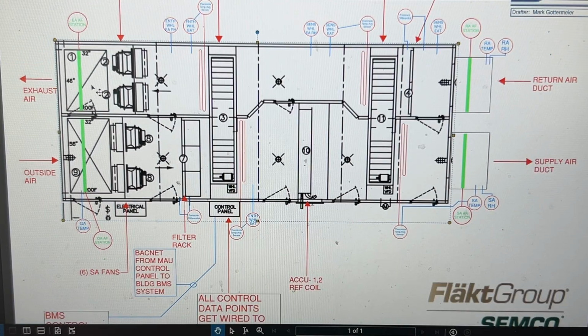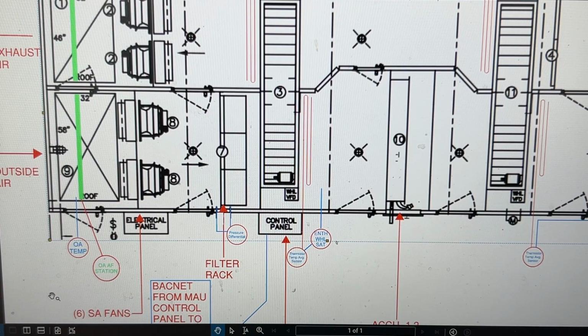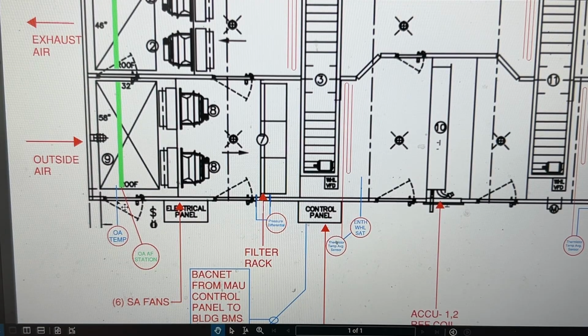And the purpose of these, we've got 4 of them on this unit: one at the outside air inlet, one at the exhaust air outlet, one here at supply air serving the building, and one here at return air coming back from the building. The purpose of those is just to be able to monitor whether we have airflow at that point or not. So a control point here on this outside air coming in is an outside air temperature sensor. That has a probe inside there, which lets our graphic know what that outside air temperature is. It also comes back to this control panel.